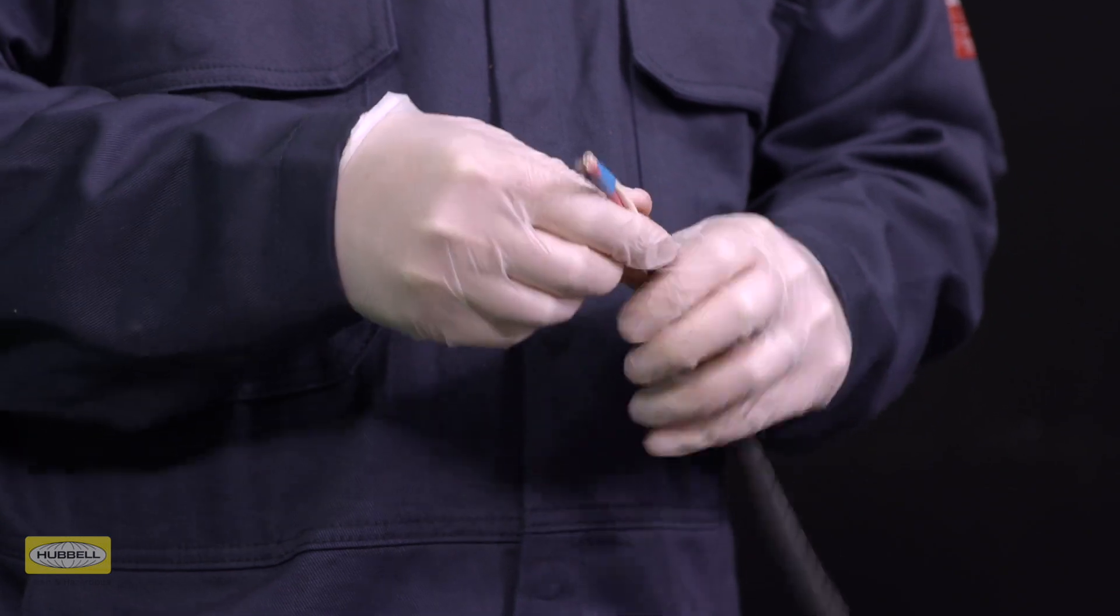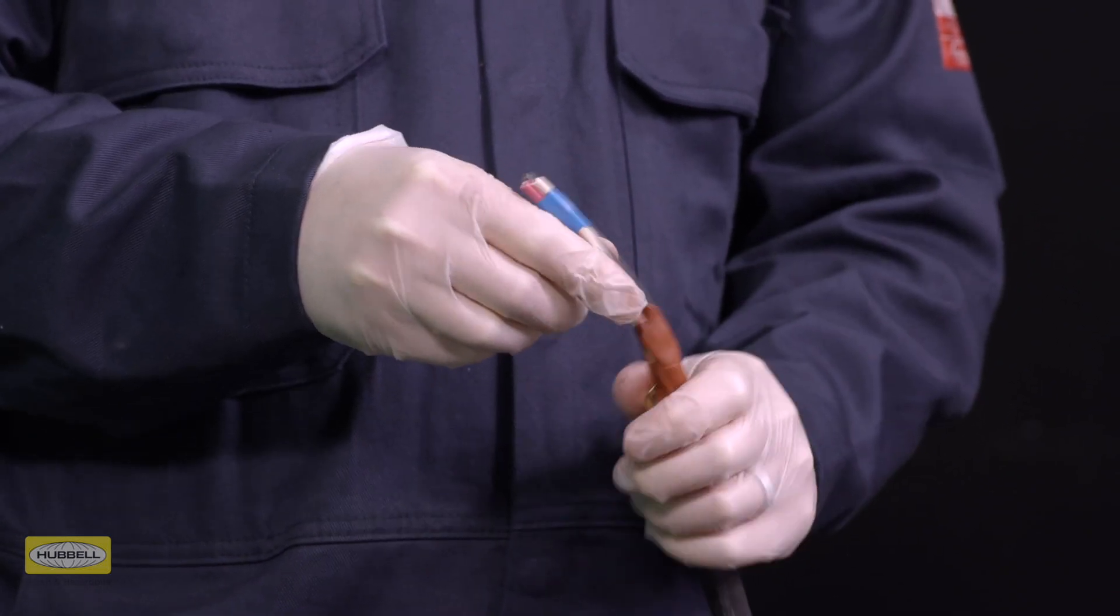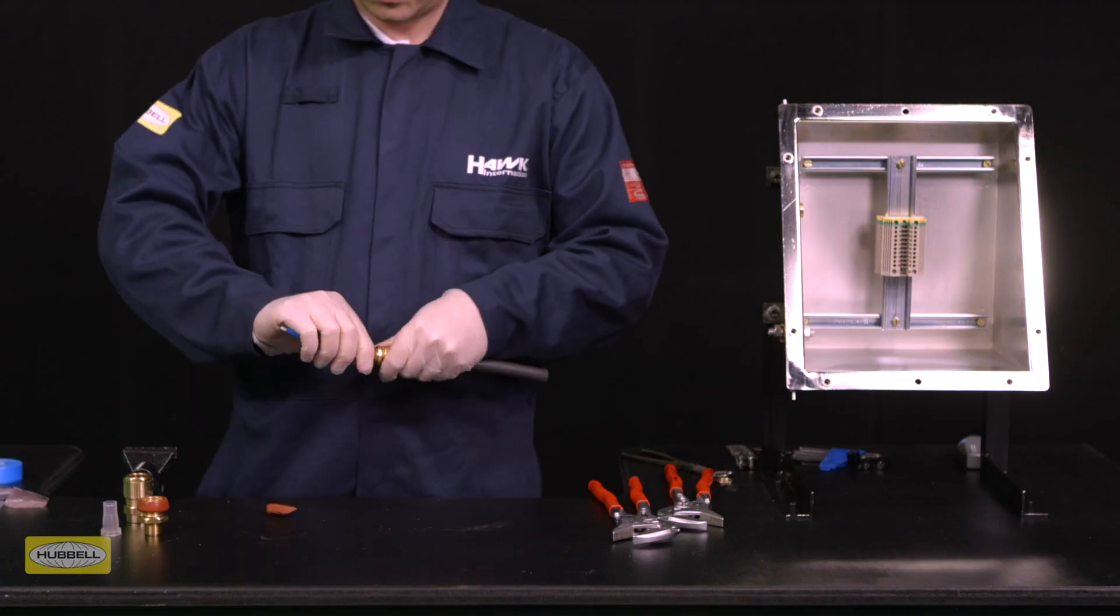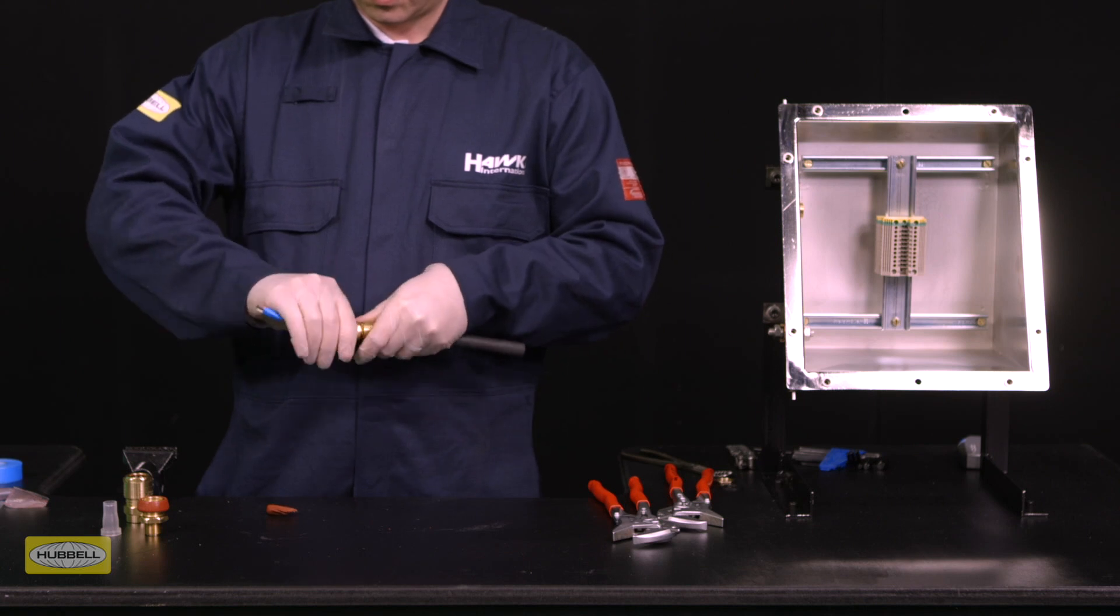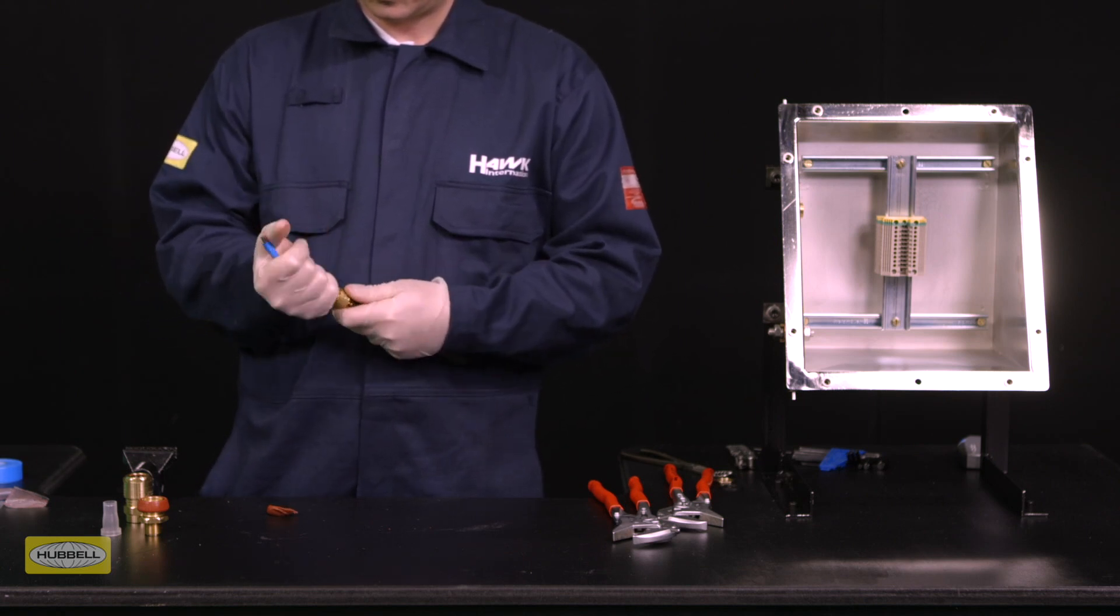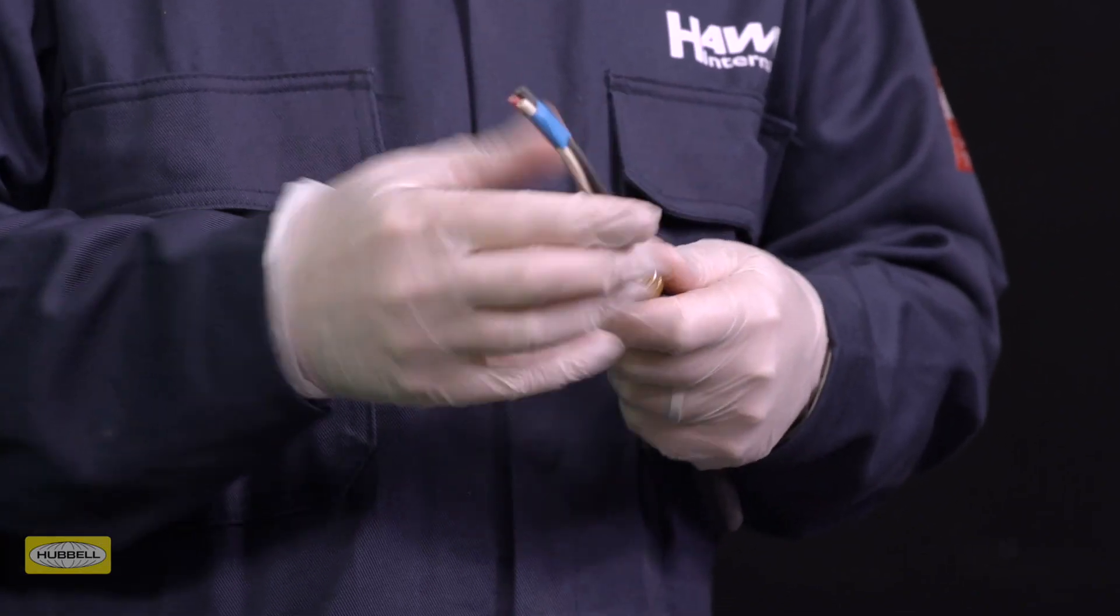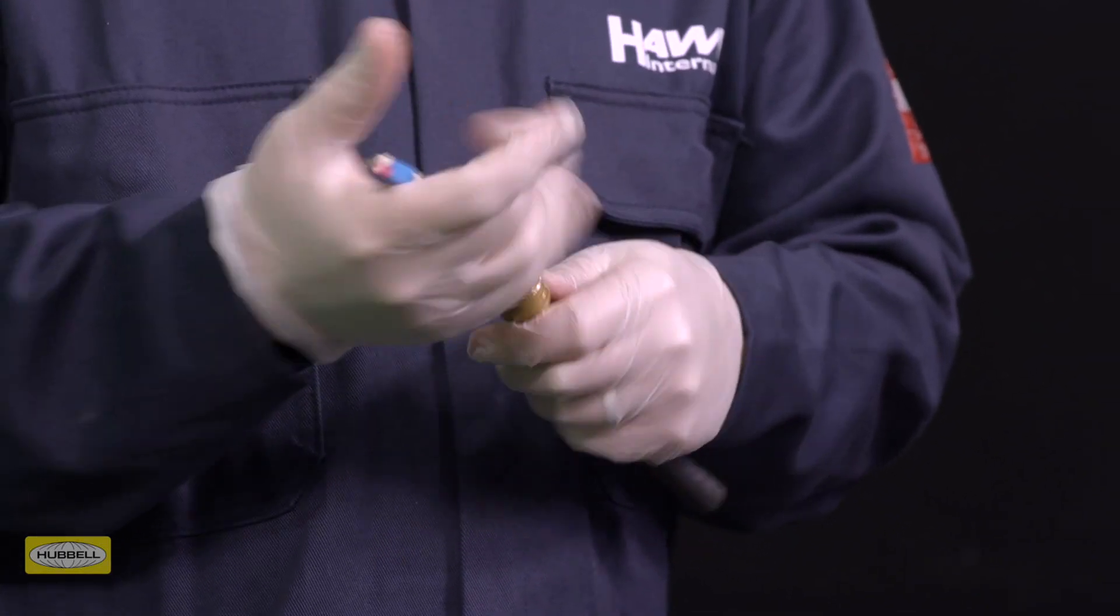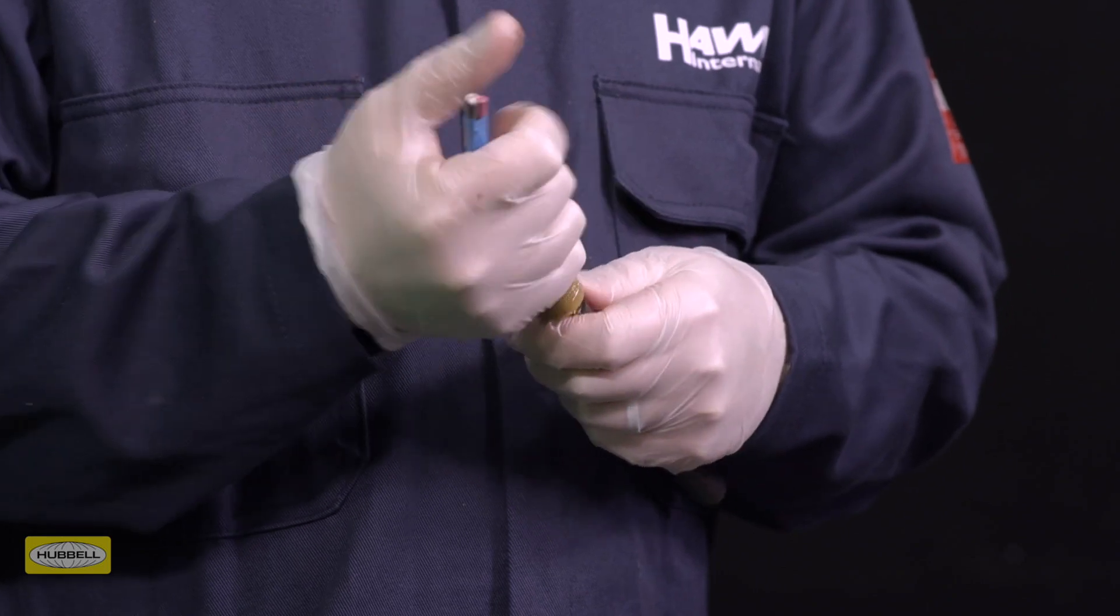Pack more compound around the outside of the conductors. Shape the compound using the palm of your hand. The compound should form a cone shape to aid installation and reduce the risk of voids during pot installation.